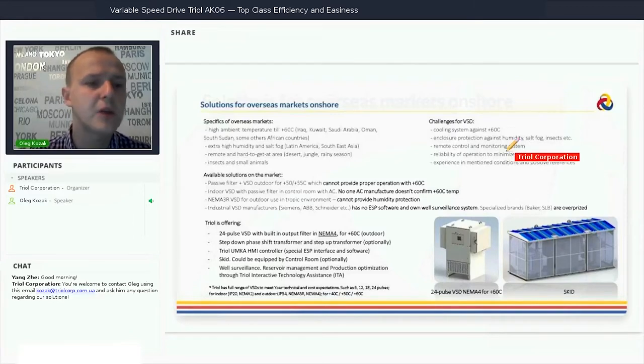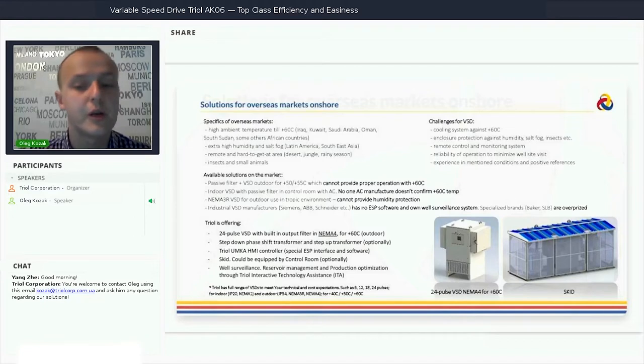So to avoid any risk of overheating, we propose the next solution: a 24 pulse VSD with output sine wave filter, which guarantees stable work with any humidity, up to 100% humidity, and plus 60C ambient temperature, for outdoor solutions.